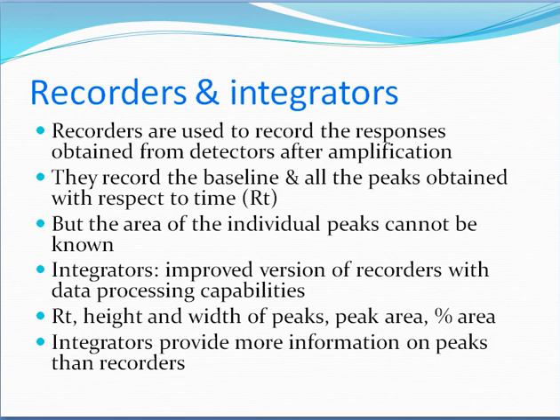Recorders are used to record the response obtained from the detector after amplification, recording the baseline and all peaks with respect to time, but the area of individual peaks cannot be calculated. Integrators are improved versions of recorders with data processing capabilities — they provide peak height, width, and peak area, giving more information about the peaks than recorders alone.